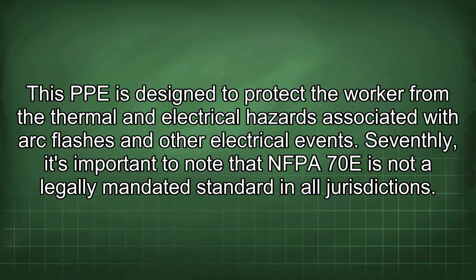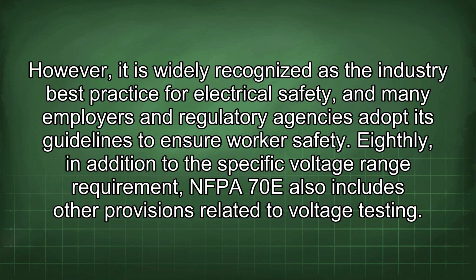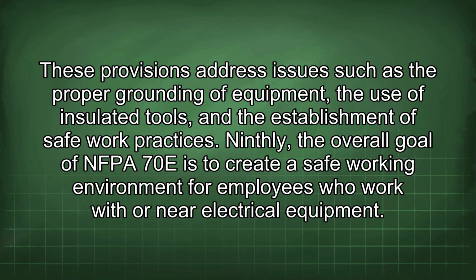Seventhly, it's important to note that NFPA 70E is not a legally mandated standard in all jurisdictions. However, it is widely recognized as the industry best practice for electrical safety, and many employers and regulatory agencies adopt its guidelines to ensure worker safety. Eighthly, in addition to the specific voltage range requirement, NFPA 70E also includes other provisions related to voltage testing. These provisions address issues such as the proper grounding of equipment, the use of insulated tools, and the establishment of safe work practices.